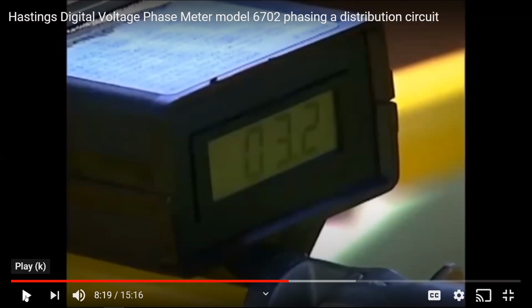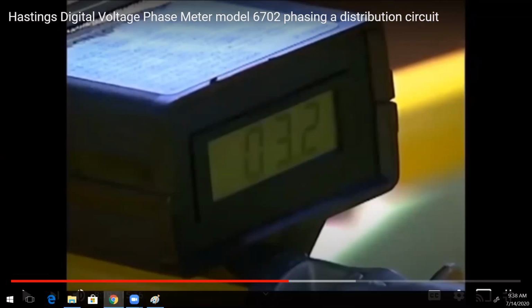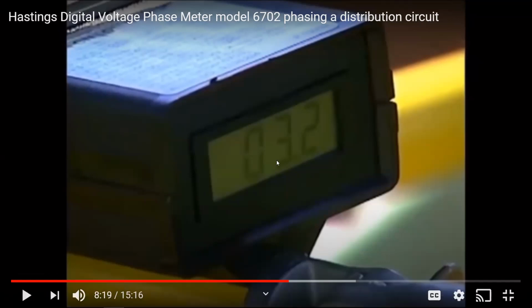What did he say his line voltage regularly was? 4,800. His line voltage, as far as AC is concerned, was actually 4,800 volts. But due to the conversion to DC with the high pot adapter, we're only going to get 3,200, which is about, what, 60% of what the conductor is. So a 3.2 reading is okay.